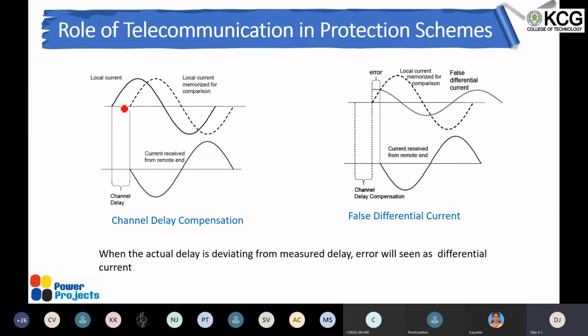So here the local end current is actually this one, and the remote end current is supposed to be exactly 180 degrees out of phase. But what happens is that there is a communication channel delay. The local end relay gets the information at this instant. For understanding's sake, we can say maybe around 4 millisecond. After 4 millisecond, the local end relay gets the information of the other end current through the communication channel.